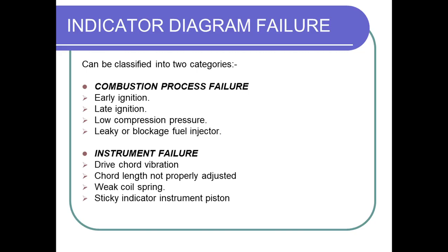Now when we speak about instrument failure: drive cord vibration, cord length not properly adjusted, weak coil spring, sticky indicator instrument piston. So these are the key points that we are supposed to remember, express, and tell to the surveyor when we are answering the question.